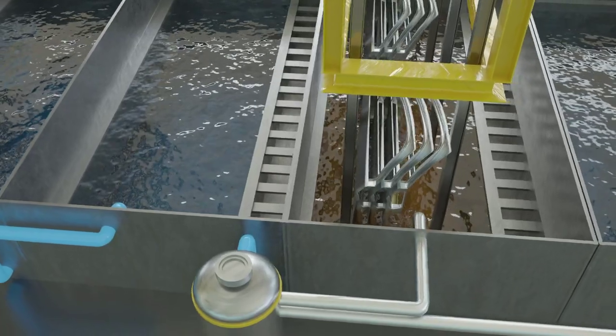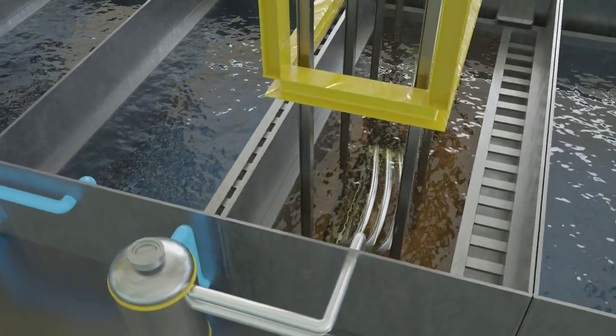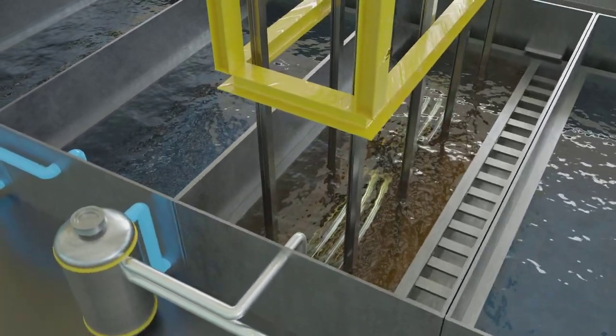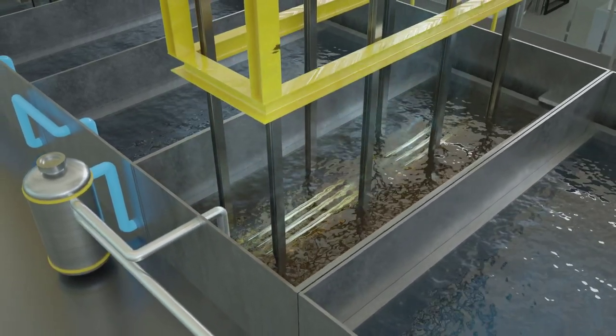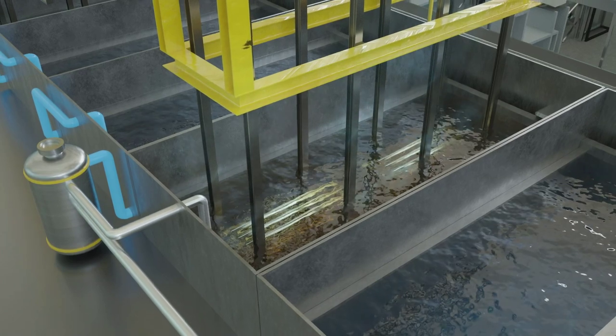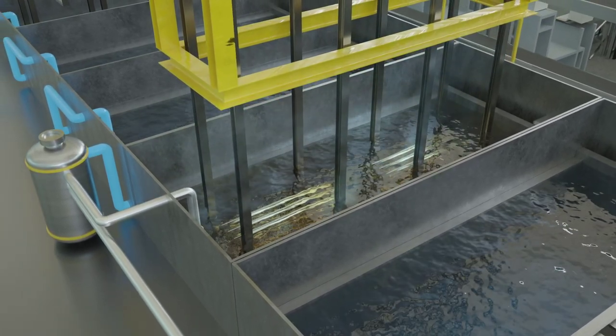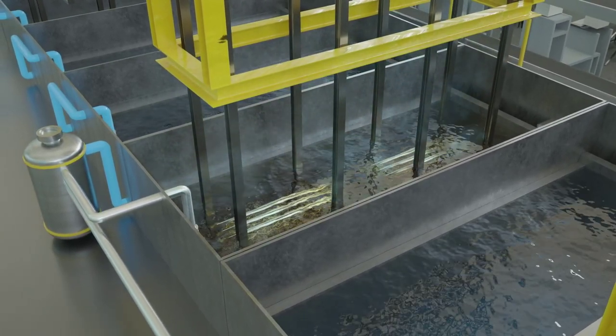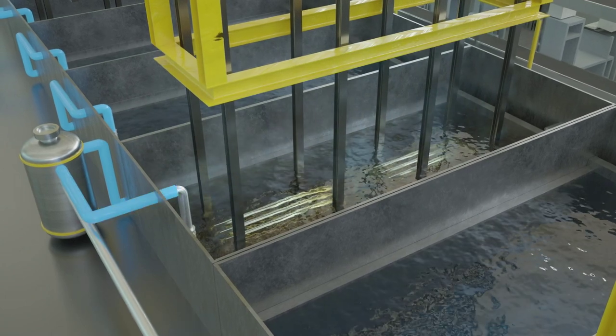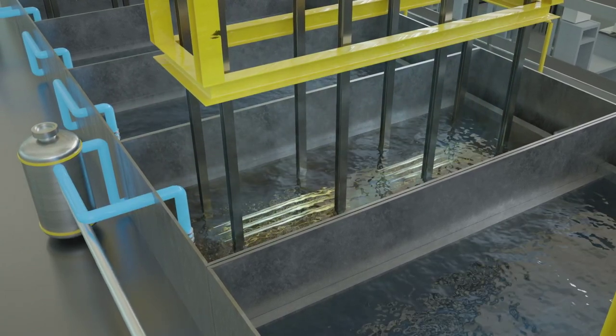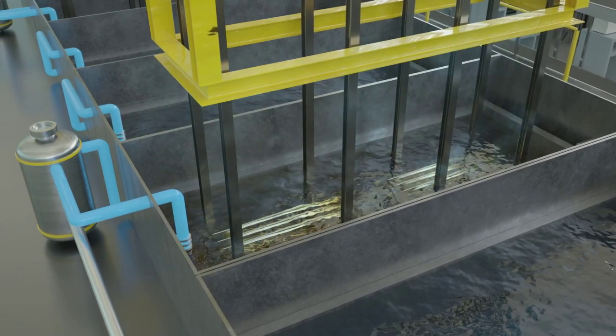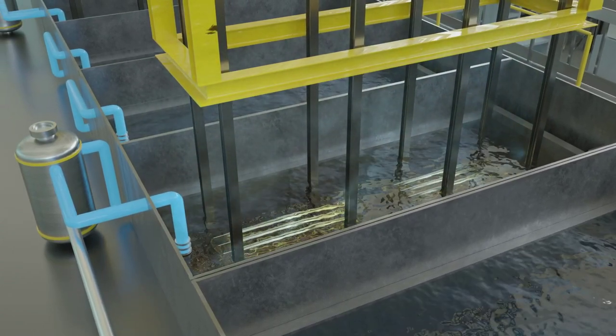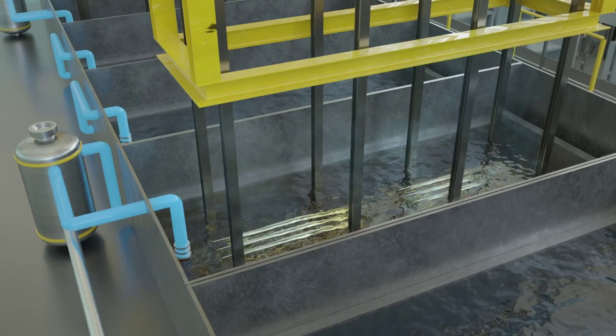Directly in front of this rinsing cascade is the degreasing bath, in which the components are actually cleaned using chemicals and ultrasound. Water is lost here due to evaporation and drag-out losses. The buffer storage tank compensates for this with the aid of the rinsing water. This contains the surfactants washed off in the cascade from the degreasing bath. They are immediately recycled here.